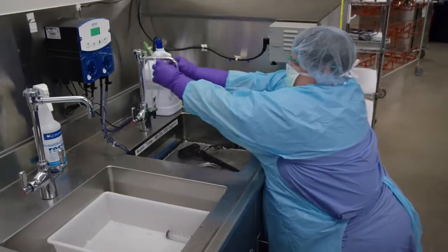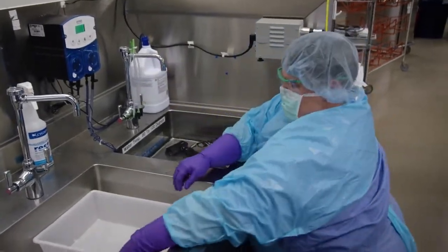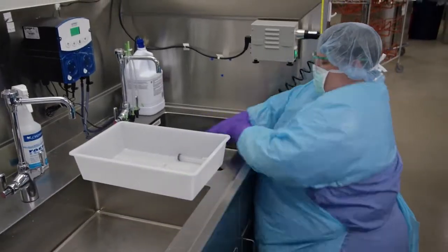The presence of air bubbles or failure to maintain pressure during testing is a positive indicator of a leak. Doing a leak test takes some time because you really have to watch for those bubbles or watch to see if the pressure drops in each different configuration as you turn those knobs.